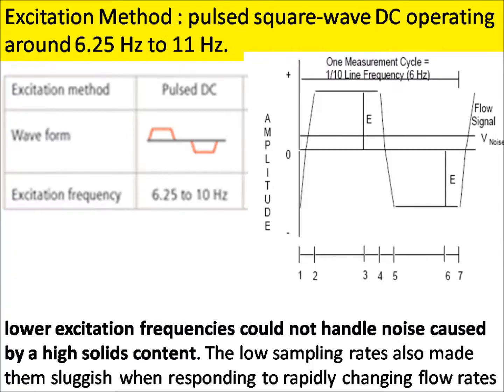As magmeter technology advanced, the next generation excited the coils with pulsed square wave DC operating around 6.25 Hz to 11 Hz. This worked well enough in most situations and delivered the sought-after zero stability. But lower excitation frequencies could not handle noise caused by a high solids content. The low sampling rates also made them sluggish when responding to rapidly changing flow rates.